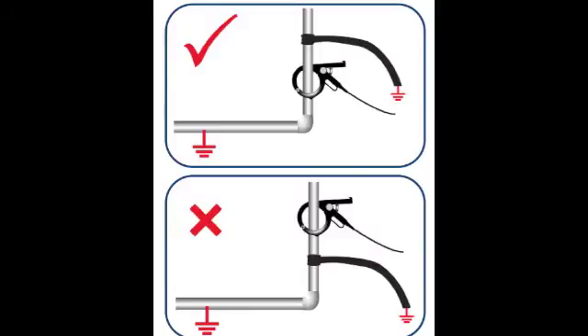To use a clamp, the target line must be grounded on both ends. The clamp works by electromagnetic coupling. It induces a current on a closed loop, so you must connect the clamp below a nearby grounding point.